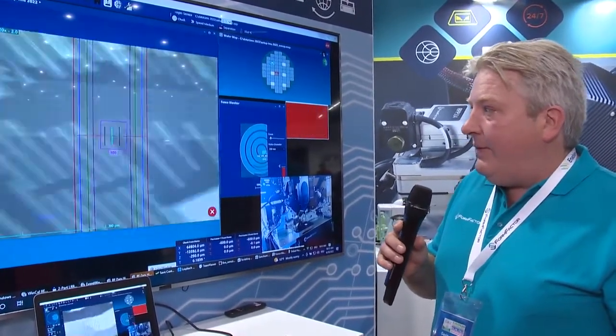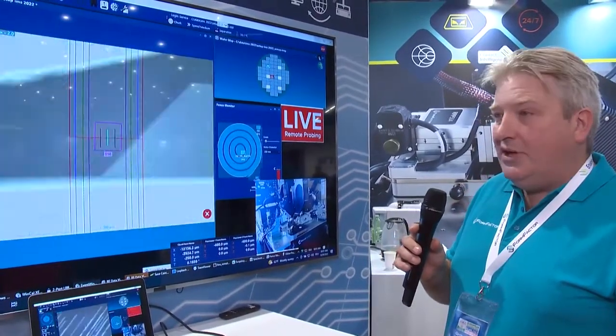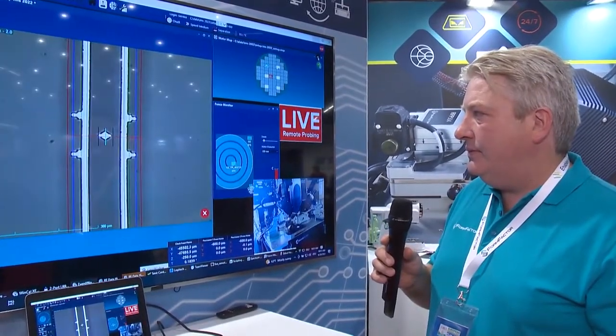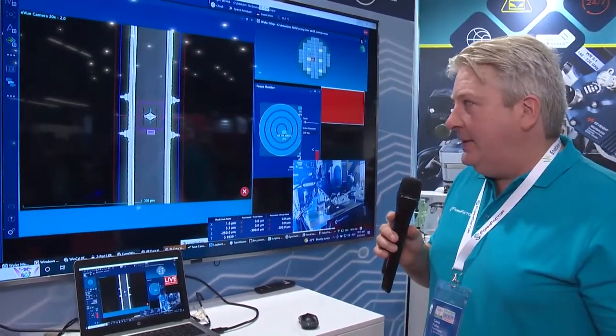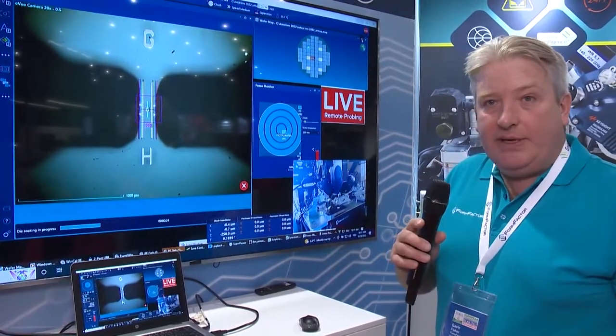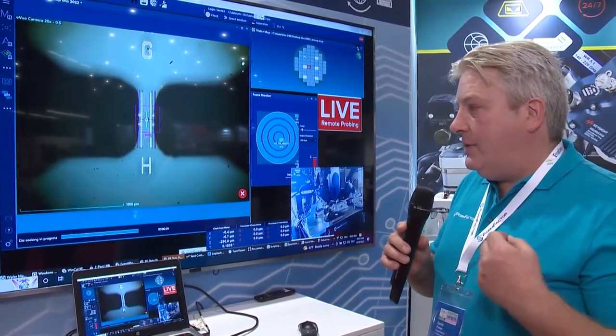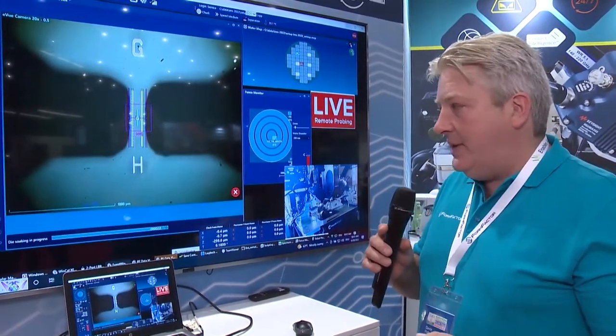System now is doing an alignment of that wafer. It's a view track align, to make sure it's all correctly aligned, which is useful at temperature. Not essential because the system does do adjustment from each die step. And with that done, it will basically be viewing its transition as being complete, and then it effectively hands over the prober back to the test executive. All the activities that you just saw happening a moment ago were purely autonomous. The test executive did none of those things. It was purely the system getting itself in a state, corrected and ready for work, ready for measurements.